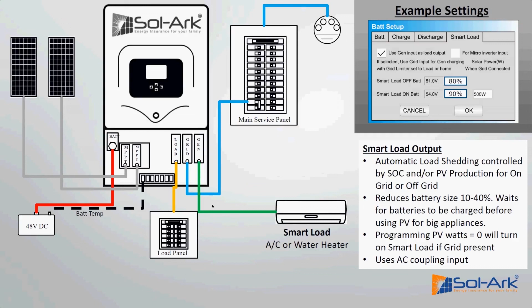Also, if you use AC coupling, you're going to use up the generator breaker port, whether you put it on the load panel for load-side AC coupling or on the generator for gen-side AC coupling. Either way, it uses up the port, so you can't have something AC coupled to the load panel and still use smart load. There's a bit of a trade-off there, but at least you have options.